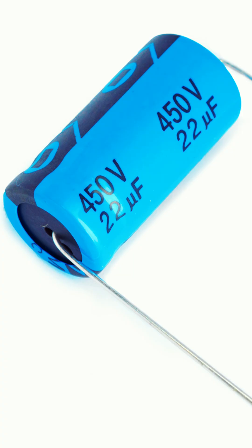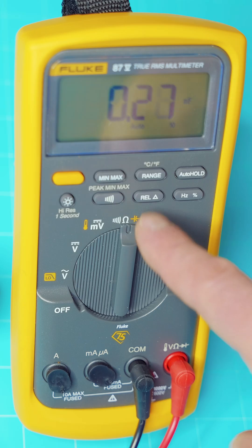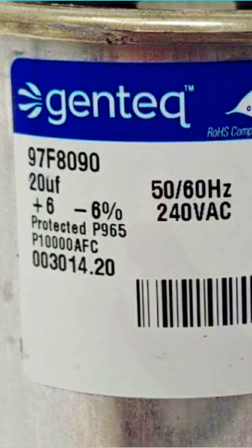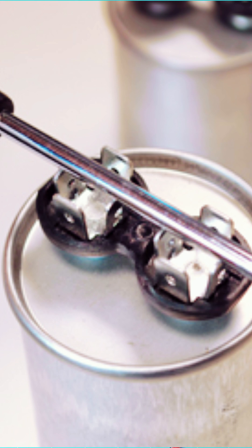And that's it folks. You can check pretty much any capacitor that you want in this manner. Just make sure you have a meter capable of measuring capacitance and then read your label to be sure you know what the tolerance is and what you're supposed to be getting. And of course, be sure to discharge those contacts before you ever test these.